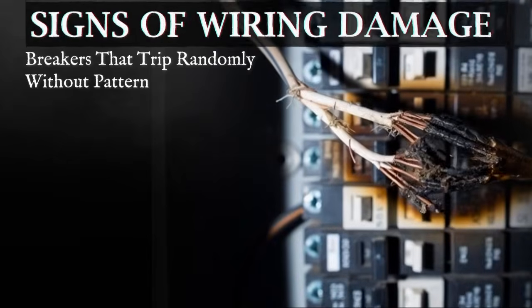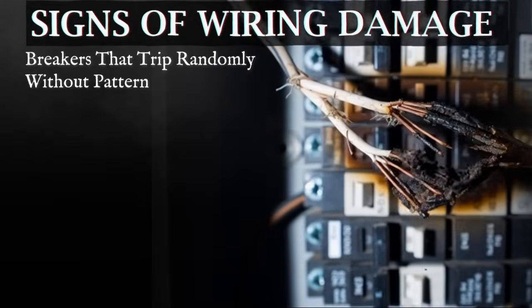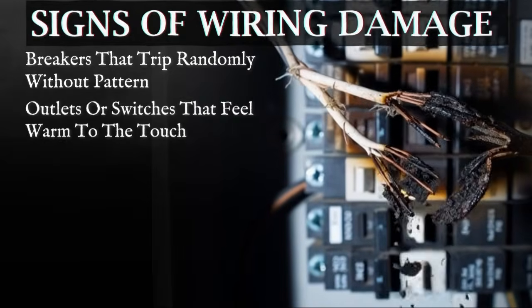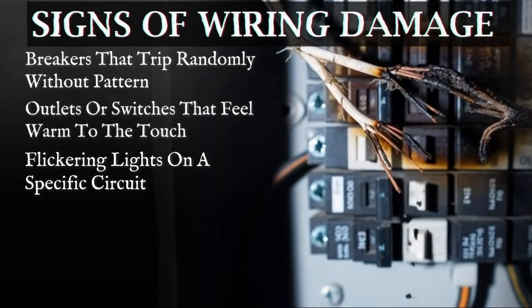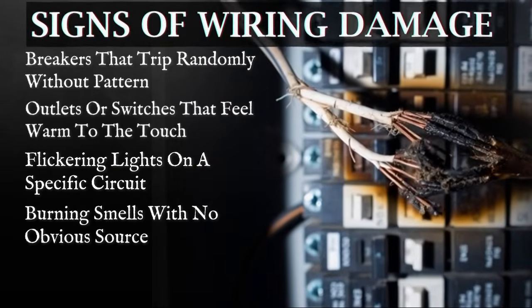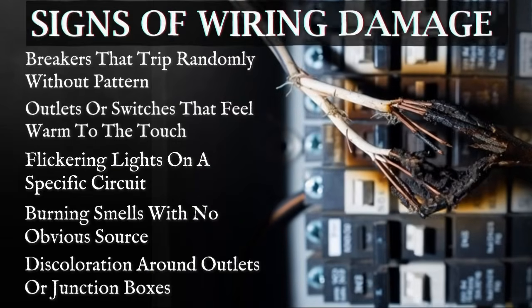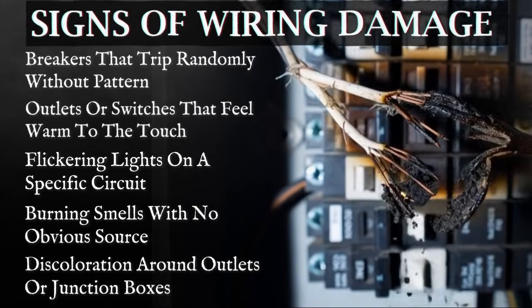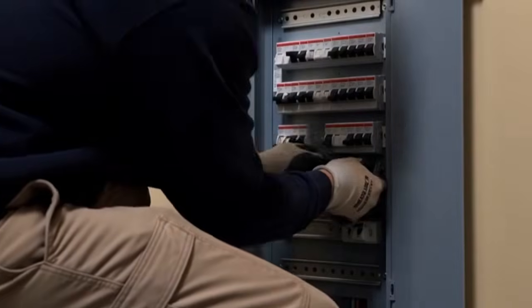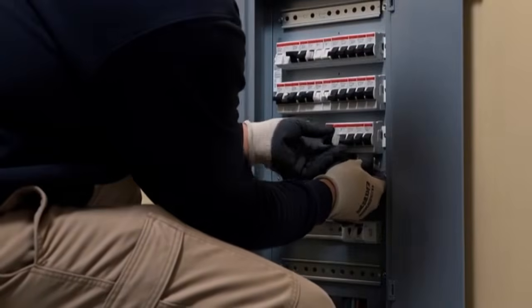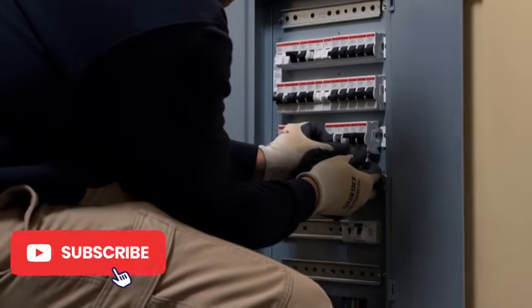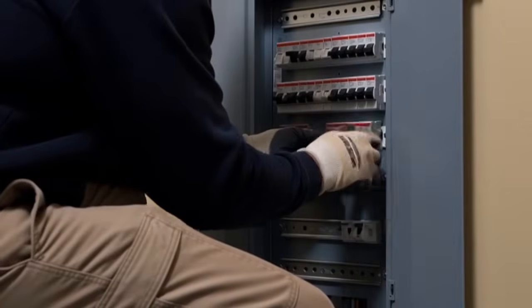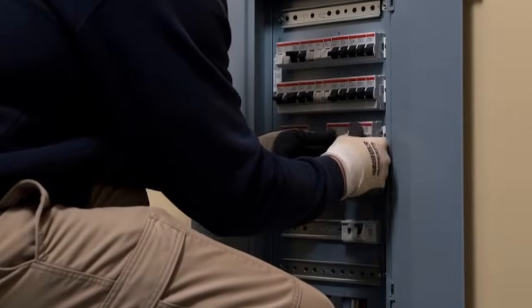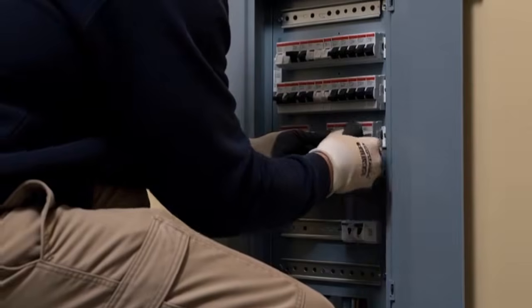Signs of wiring damage include breakers that trip randomly without pattern, outlets or switches that feel warm to the touch, flickering lights on a specific circuit, burning smells with no obvious source, and discoloration around outlets or junction boxes. If you suspect wiring damage, this is not a DIY diagnosis. You need an electrician who can systematically test the circuit, inspect accessible junction points, and potentially use thermal imaging to identify hotspots hidden inside your walls.